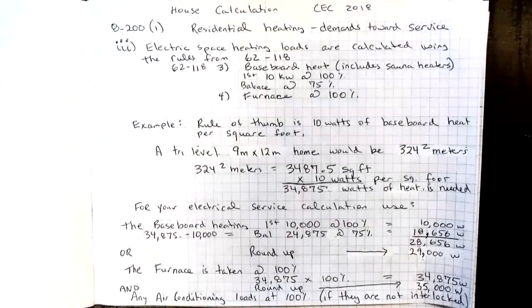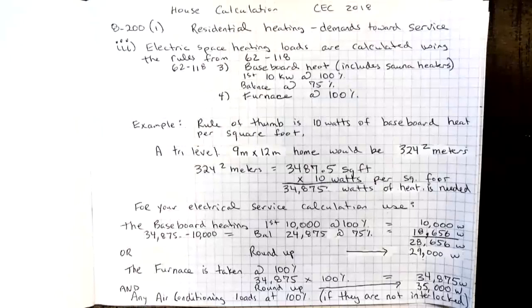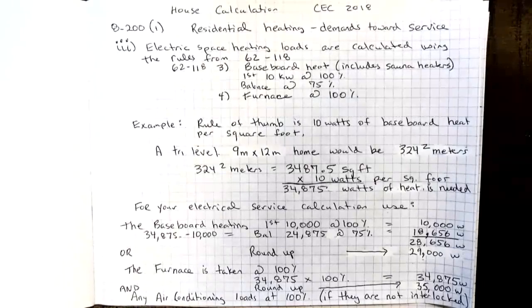In a previous video, I spoke about how many watts baseboard heat we need per square foot. It's generally acceptable that we use 10 watts baseboard heat per square foot. In this example, a tri-level 9 meter by 12 meter home would be 324 square meters. If I convert that, I get 3,487.5 square feet times 10 watts per square foot gives me 34,875 watts that I need.